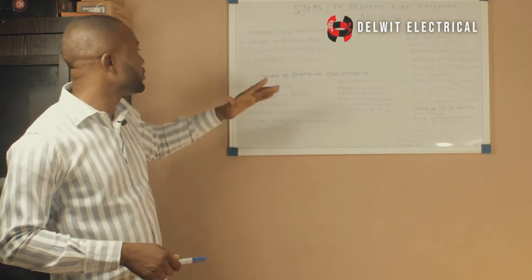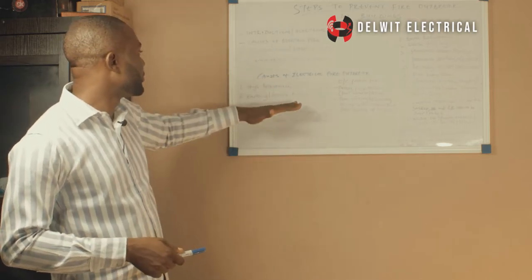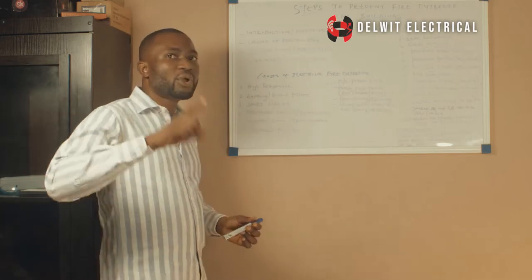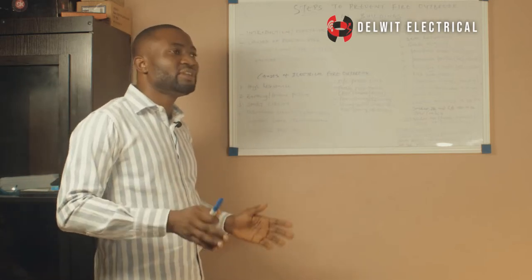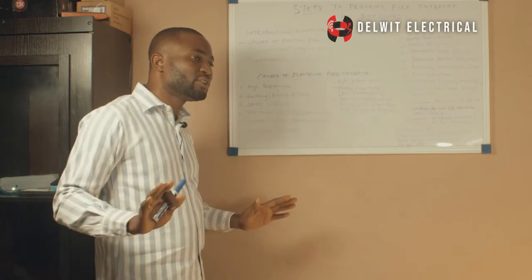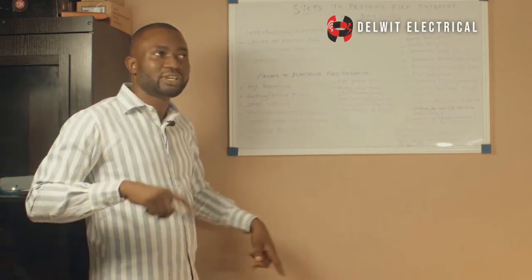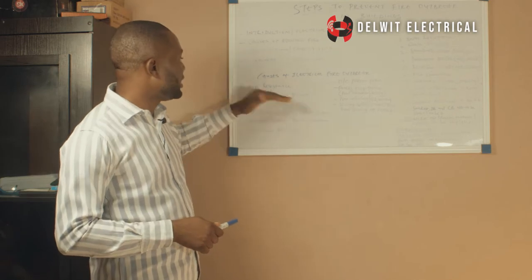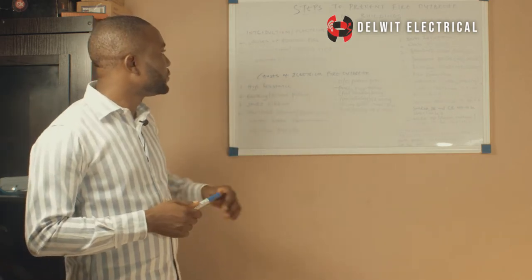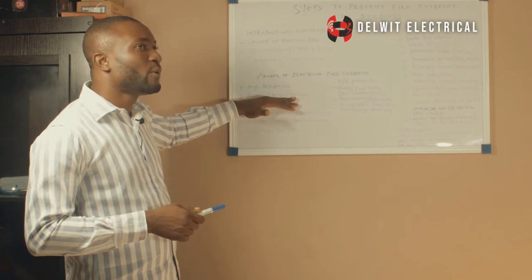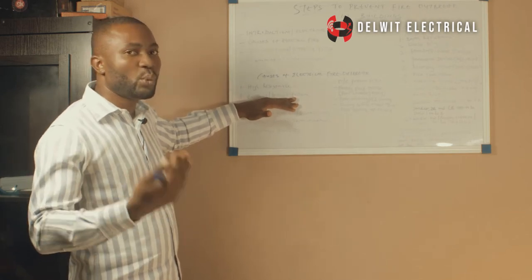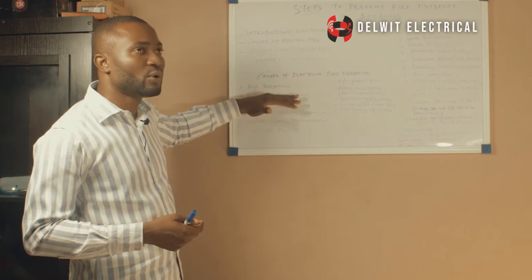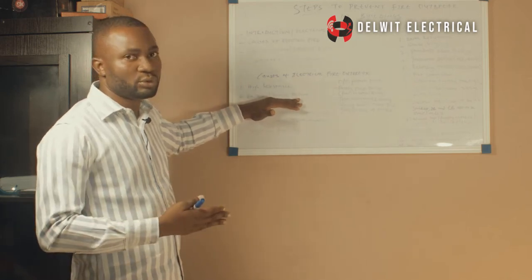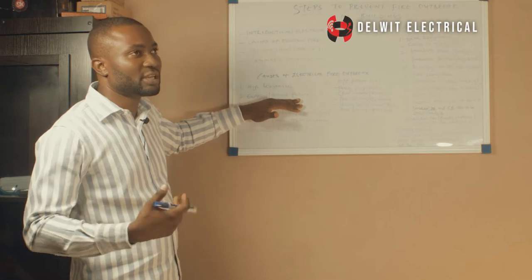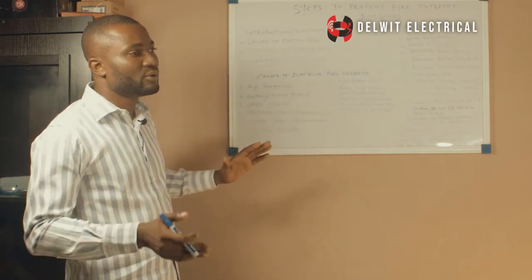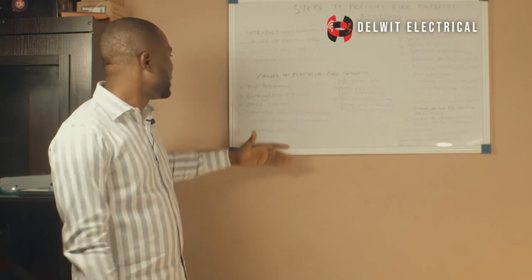The second one on the causes of electrical fire outbreak is earthing, or ground failure. When your earthing fails, you will discover that everything about earthing on that building is gone. Even if you have your earth rod and everything on the ground, it's gone. I told you earlier that I'm going to show you an equipment for how to test for that. If you don't carry out an earth resistance test, there's no way you will determine if your earth has failed or not. Because when you are doing the test, maybe you got 2 ohms. After a year or two, you might be getting 20 something, 30 something. In that case, that earthing has failed. You have to do a new one, or you treat that particular one.